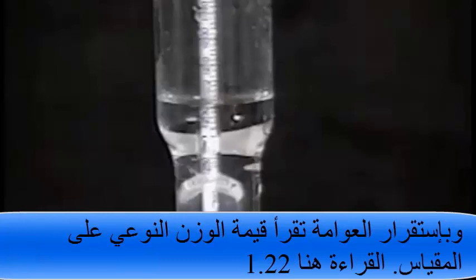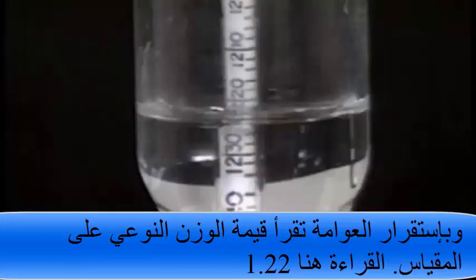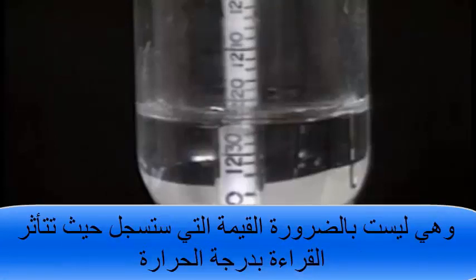If the specific gravity is high, the float will ride high in the sample. If the specific gravity is low, the float will sink lower into the electrolyte. Once the float steadies, the specific gravity is read off the scale at the surface of the electrolyte. The specific gravity reading here is 1.22.